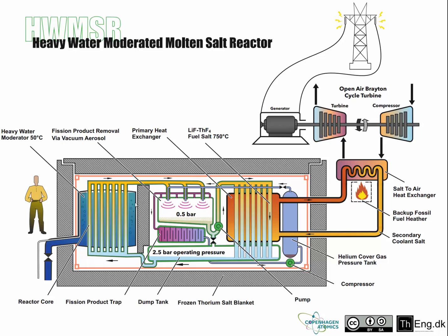Let's talk about what's inside the container in this conceptual drawing. There's the reactor core — the reactor core is a thermal core and it needs to be moderated. This can be done in two ways, either with graphite or with heavy water. In this drawing we have shown heavy water. We are still researching whether heavy water can be used, but there are good indications that heavy water will be less problematic to decommission after use than graphite, and also that it gives you a better neutron economy. There are still other problems that need to be solved but we are working on those.